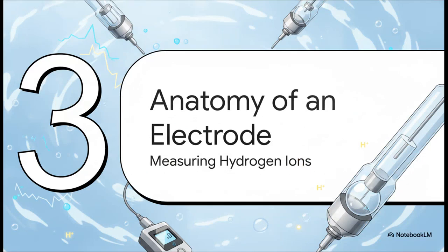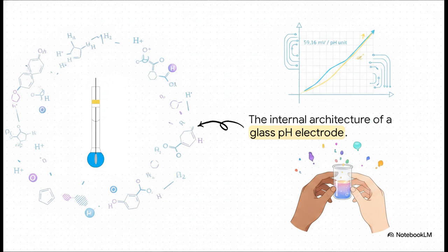Which brings us to Section 3, anatomy of an electrode. So how do we actually measure these microscopic, totally invisible hydrogen ions? Well, inside the architecture of a glass pH electrode, you've got a device that generates an electrical voltage that's strictly proportional to the hydrogen ion activity. The Nernst equation tells us we should see a slope of about 59.16 millivolts for every single unit change in pH. But, an electrode doesn't just work alone.